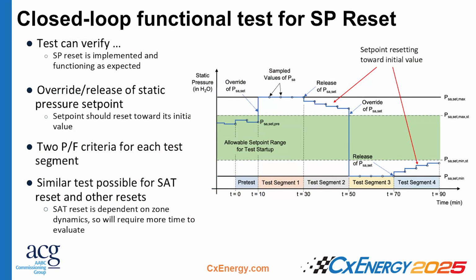The first one is a specified strategy that we have in our closed loop functional testing guide for air handling units. In this case, we're looking at overriding the pressure set point at the air handler to drive the fan speed up to its max or down to its minimum. If you drive the air handler to its max, the idea is that with Guideline 36, your underlying requests are going to go down because of all the airflow you're putting into your space. Once the VAV dampers are all in deadband mode, now you could release that pressure set point.